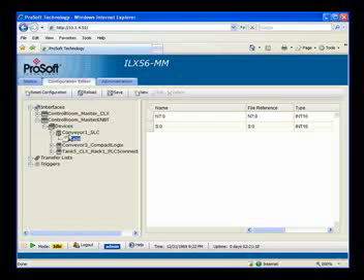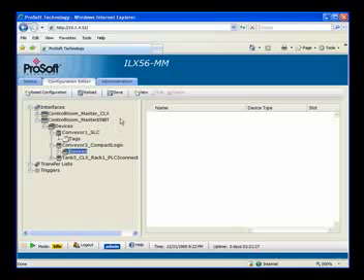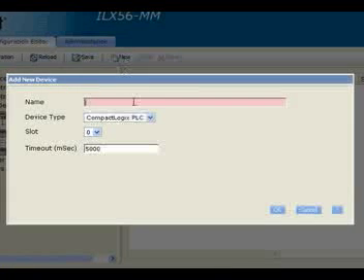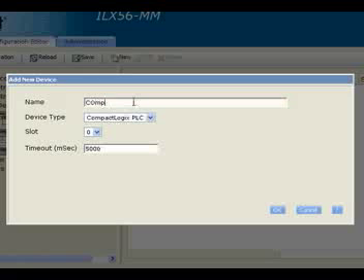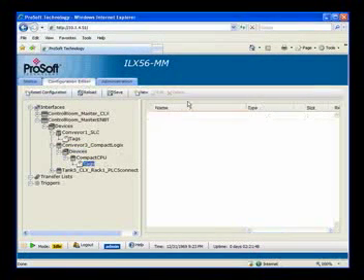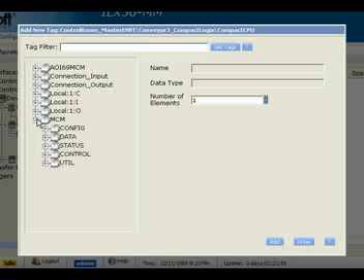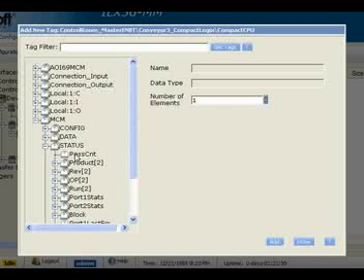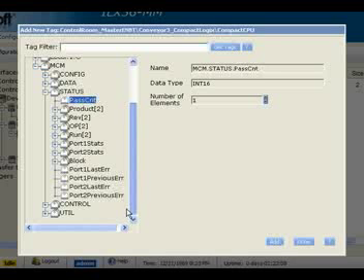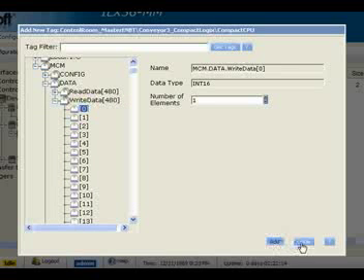Let's add tags for our CompactLogix. Before we do that, we have to add the CompactLogix CPU — I'll click New and add it. CompactLogix CPU is always slot 0. Now I'll click New Tag; the tags are interrogated by the module. I'm going to select the PassCounter — that's a counter always counting within the module, currently for the MCM Modbus communication module, making it a good value to pass to another processor. I'll click Add, then also select our WriteData0 tag and click Add. Now we see our two tags.